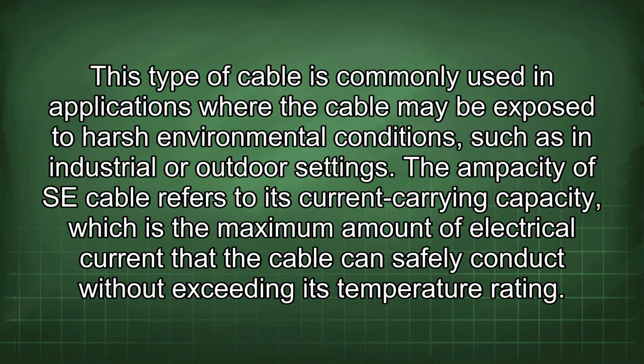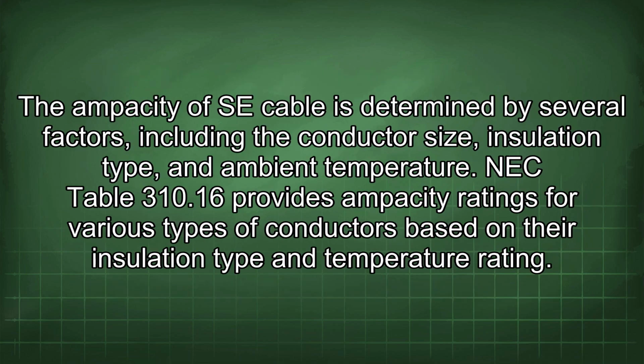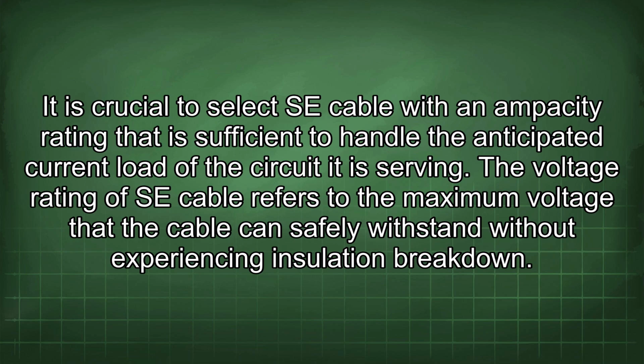The ampacity of SE cable refers to its current carrying capacity, which is the maximum amount of electrical current that the cable can safely conduct without exceeding its temperature rating. The ampacity of SE cable is determined by several factors, including the conductor size, insulation type, and ambient temperature. NEC Table 310.16 provides ampacity ratings for various types of conductors based on their insulation type and temperature rating. It is crucial to select SE cable with an ampacity rating that is sufficient to handle the anticipated current load of the circuit it is serving.